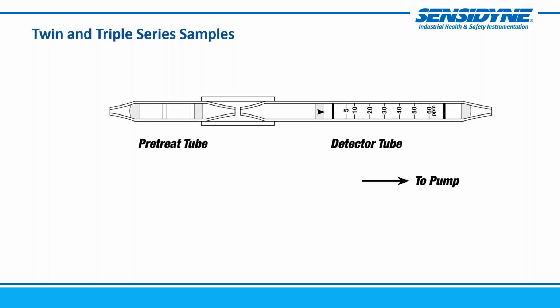And that's in order to get the chemical reaction necessary for the final detector tube reagent to react properly and change color. So one of the things that you'll see with a twin or triple series box of tubes is there'll be a kind of a rubber tube section that you will use to connect the pre-treat tubes in line with the detector tube. And again, the pre-treat tubes will always go on the opposite side of where the arrow is pointing. So upstream from the sampling pump and upstream from that final detector tube.